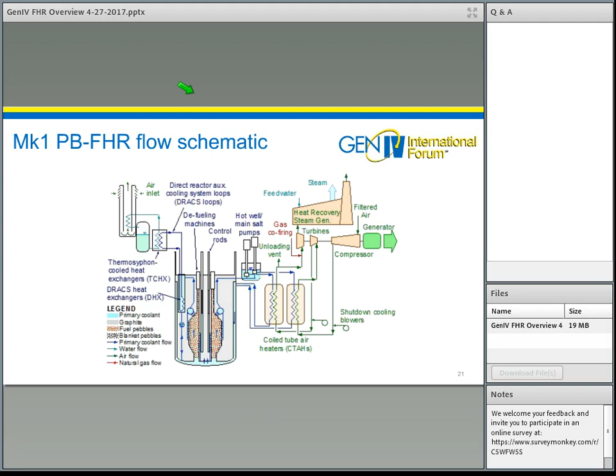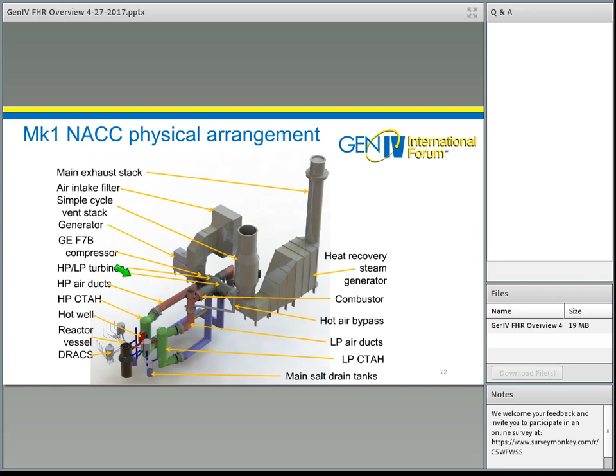So this is the physical arrangement of the equipment. What you see over on the right here again is a conventional GE combined cycle plant, except that the airflow has been diverted to the right so that the heat recovery steam generator can be offset. This allows modules to be placed physically closer to each other. You can see relatively large air ducting is used to bring the air over to these coiled tube air heaters. And then here's the reactor vessel, the direct reactor auxiliary cooling systems, and the hot well that circulates the salt through the heat exchangers, then back into the reactor vessel.